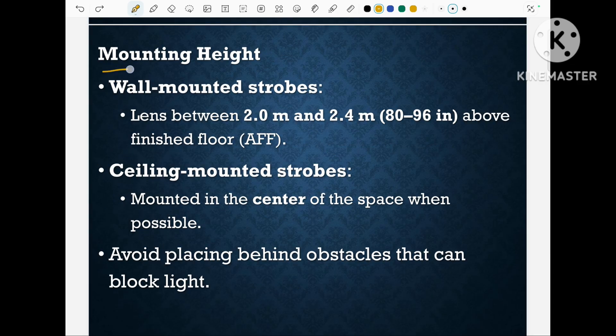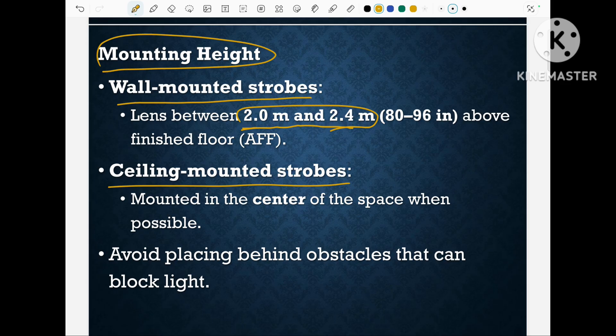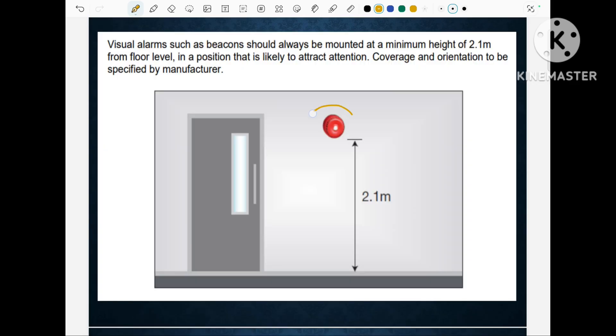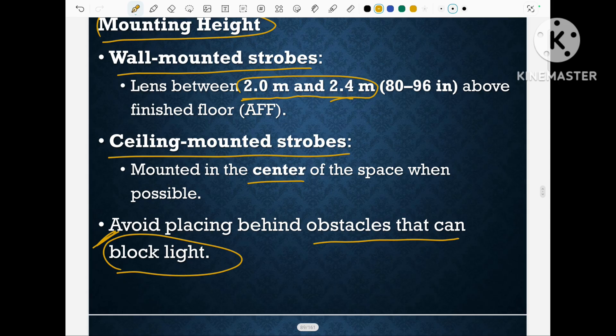Regarding the mounting height of strobes: if the strobe is wall mounted, the distance from the FFL (finishing floor level) should be 2 meter to 2.4 meter. If it is a ceiling mounted strobe, we have to mount it in the center as much as possible and avoid placing it behind any obstacle that would block the flashing light. As shown here, the sounder is at 2.1 meter from the FFL, and the sounder with the visual alarm (strobe) is also at 2.1 meter from the FFL.